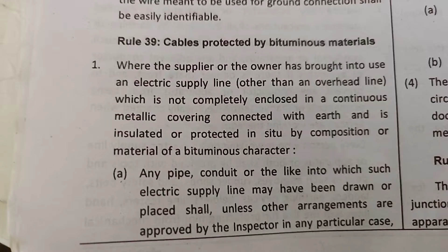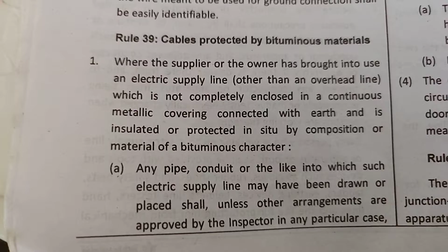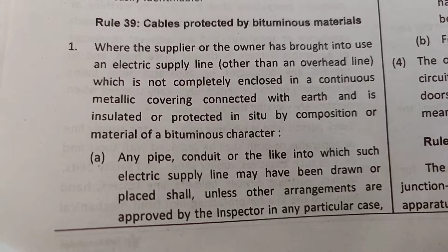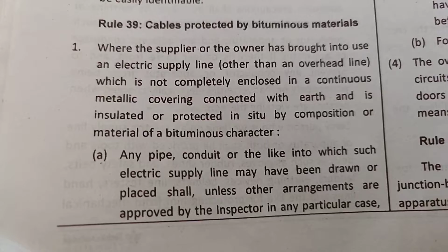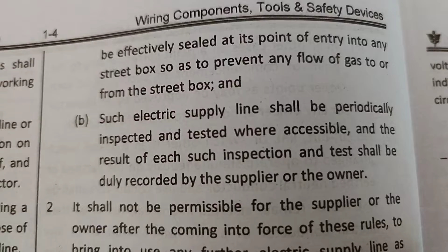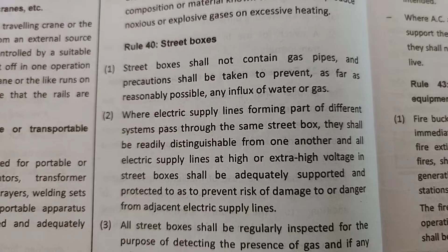Next is rule number 39. Cables protected by bituminous material. Where the supplier or the owner has brought into use any electric supply line other than an overhead line which is not completely enclosed in a continuous metallic covering connected with earth and is insulated or protected by composition of material of a bituminous character, any pipe, conduit or like into which such electric supply lines may have been drawn or placed, shall, unless other arrangements are approved by the Inspector in particular case, be efficiently sealed at its point of entry into any street box so as to prevent any flow of gas to or from the street box.